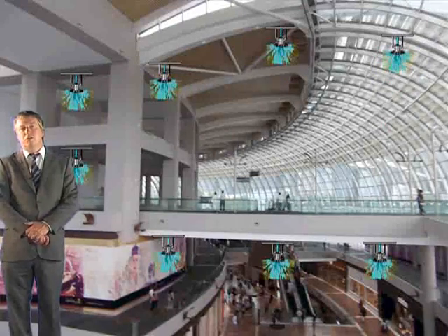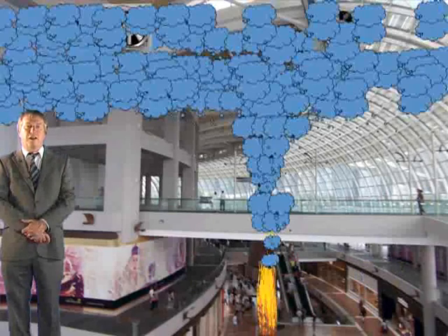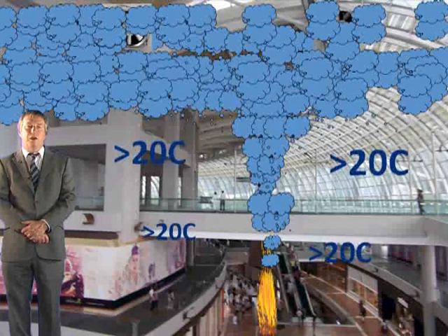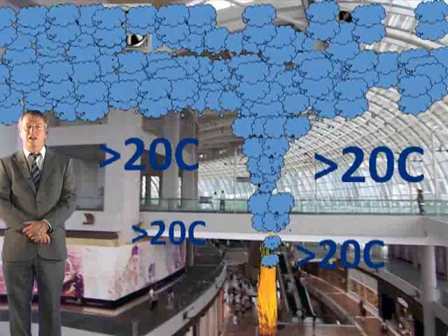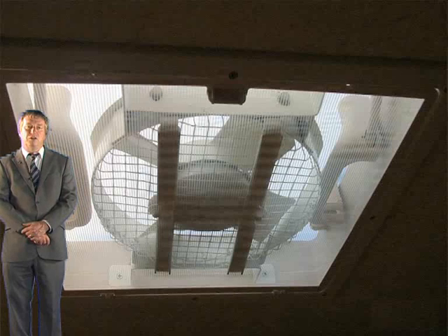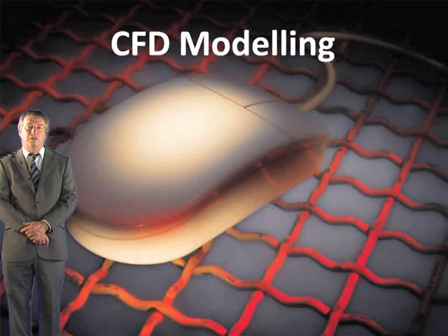Usually in these systems, the inclusion of measures to limit fire size are required, and this may include sprinklers or some other fixed installations. It also has to be ensured that the smoke has sufficient buoyancy because, if not, in a natural ventilation system, there may be insufficient buoyancy to exhaust the smoke effectively. Generally, the temperature of the gases must be at least 20 degrees C above ambient temperature. If it is any lower than this, mechanical extraction should normally be specified, or CFD modelling would be required to demonstrate that the system meets the design objectives.